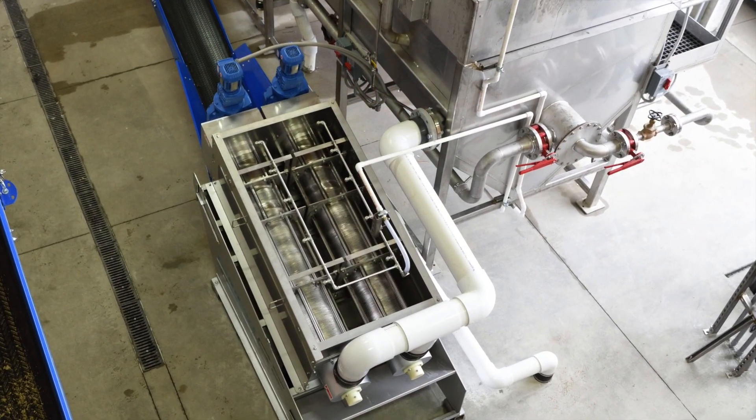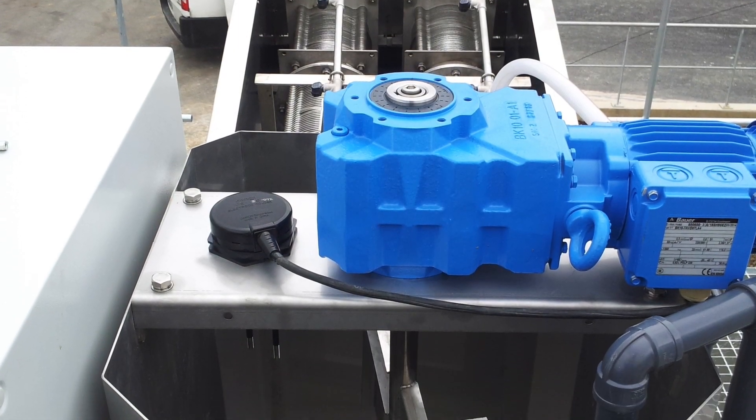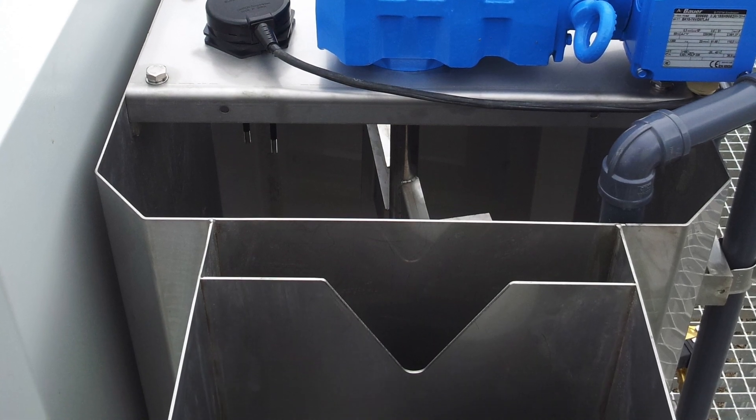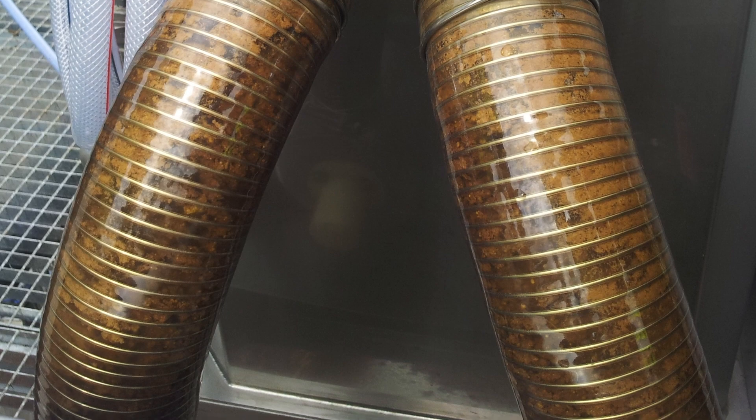Thickened sludge can flow directly into the dewatering cylinder inlet, or if polymerization is required, material can flow into the MD floc tank. After the material is flocculated, it gravity flows into the dewatering cylinder.